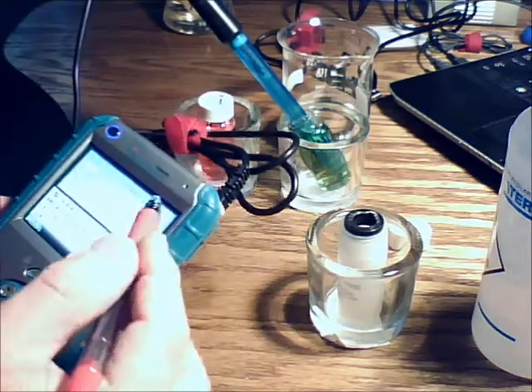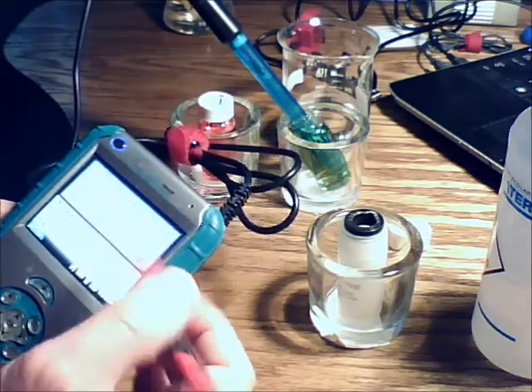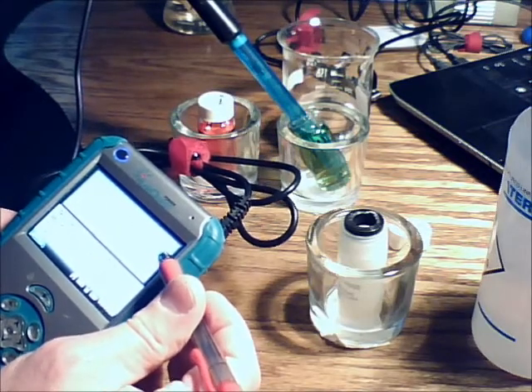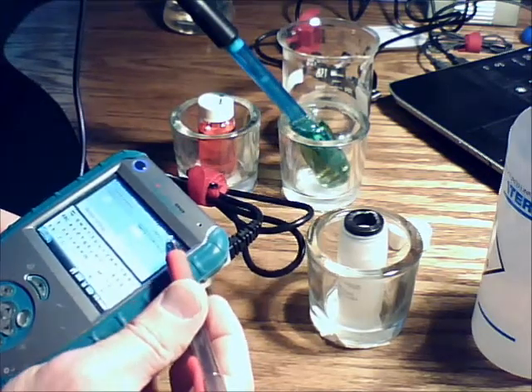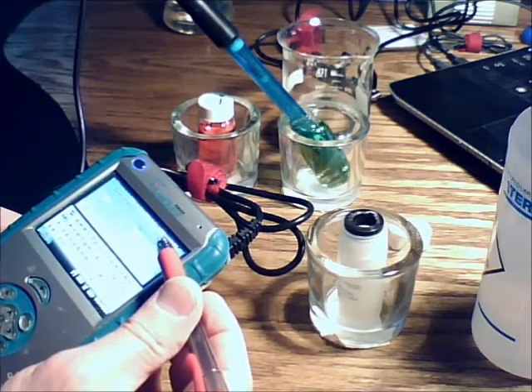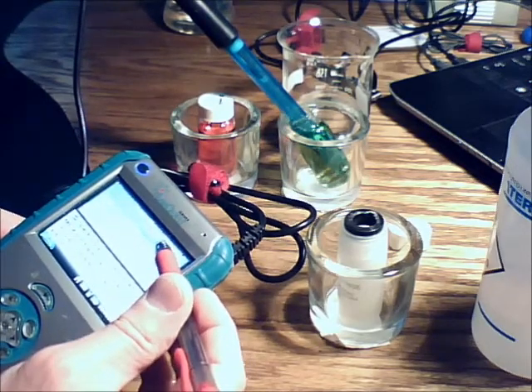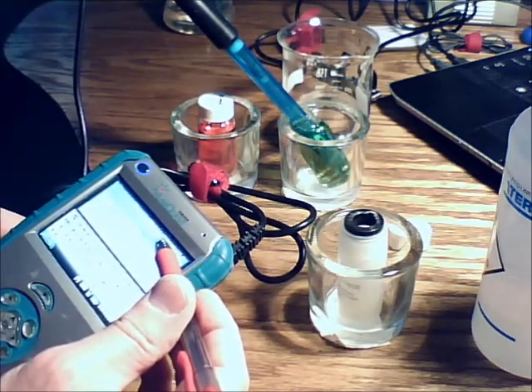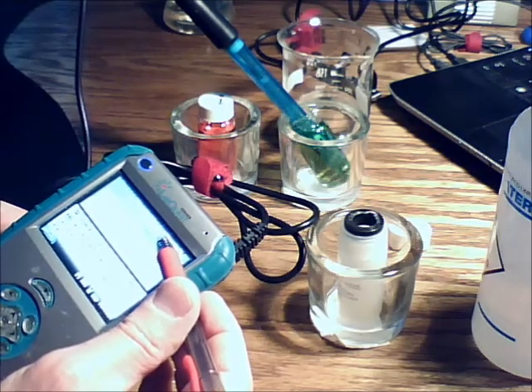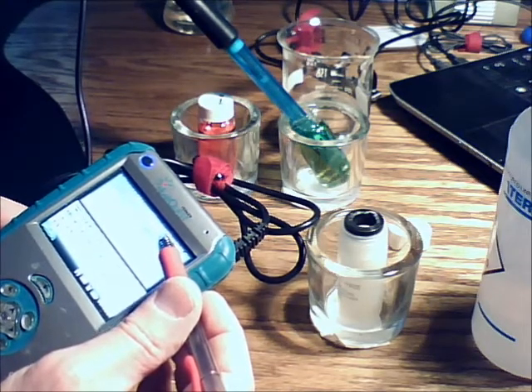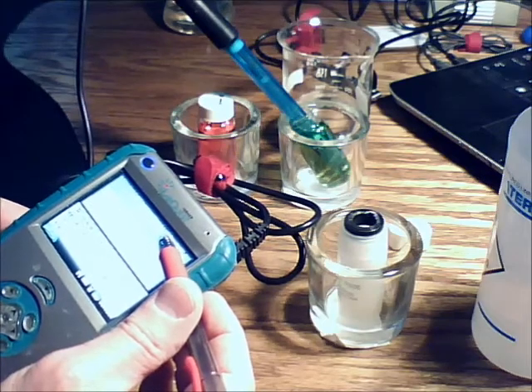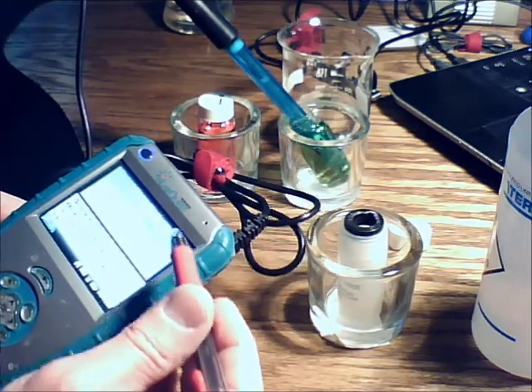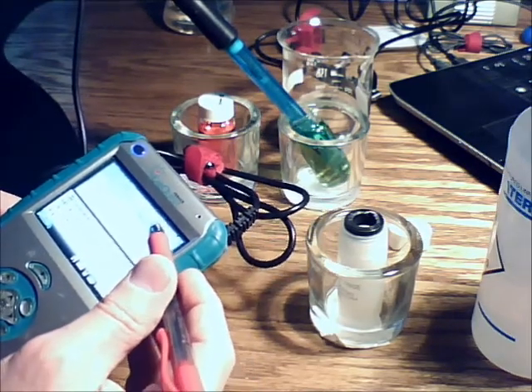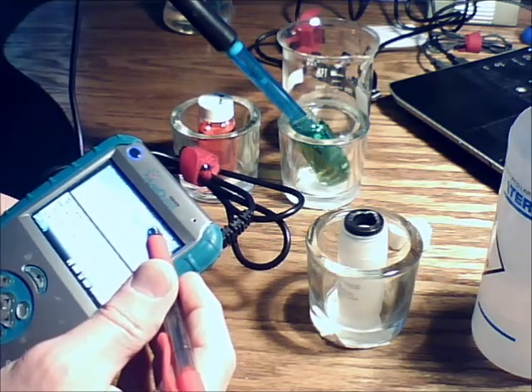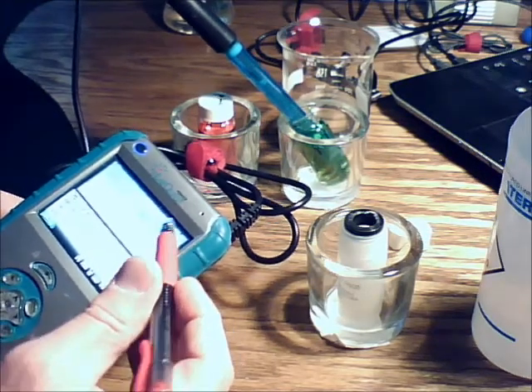And then we're going to let it settle down a minute or two. If you look at the voltage reading at the top, I'll move this up just a little bit. Maybe you can see it, maybe you can't. There's a voltage reading right here. If it's still moving around, give it a minute. And once it settles down, it won't be perfect. It may go back and forth between 0.08 volts, a hundredth of a volt, and 0.09 volts somewhere. It says 1.68 volts, and occasionally it'll say 1.69. That's okay. That's pretty settled down.